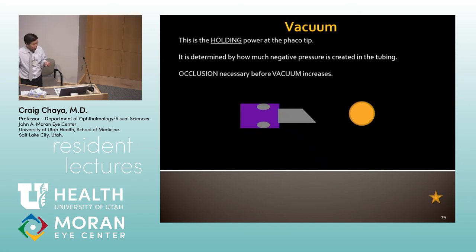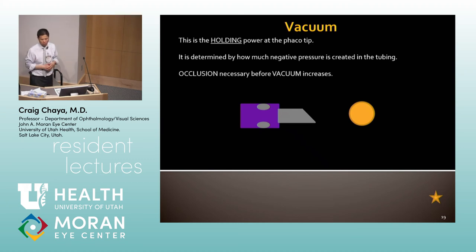There are a few phaco machines on the market that have both peristaltic and Venturi settings, which is amazing — during cortex removal you can be in the center of the eye, press on the pedal, and the cortex just comes right to your tip. Most of our machines are just peristaltic for phaco.